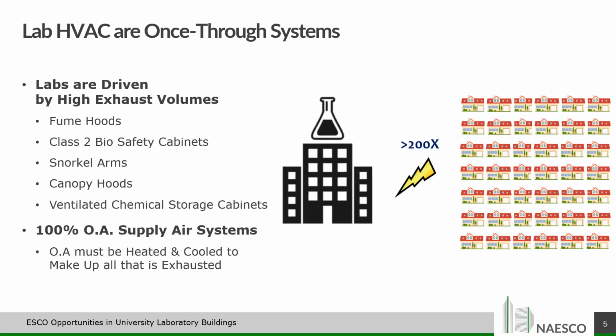Now, this air needs to be replaced with outdoor air. So, in an efficient building, you're changing the lab air out every 10 minutes with new 100% outdoor air that needs to be heated and cooled and sometimes dehumidified as well. And that's for an efficient lab. In inefficient labs, every 2 minutes you're changing out the air in that lab with 100% outdoor air that you need to heat, cool, and dehumidify. So in essence, these are once through systems. Air's coming into that lab and going right out through the roof and into the atmosphere. So it's extremely expensive to operate these labs, even when they're running efficiently. But when they're running a little bit wild, they can really get out of control.